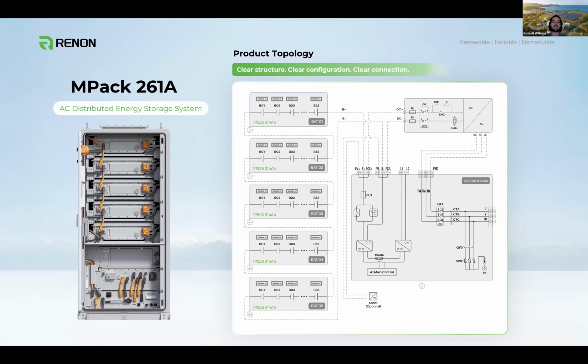The second option is a full STS system. The STS is nice because you can do two of these batteries per STS system, and that really provides instantaneous changeover. With an STS, you can have a true uninterrupted power supply for up to 500 kilowatt hours, roughly 260 kilowatts of power for instantaneous changeover. So that's really nice.